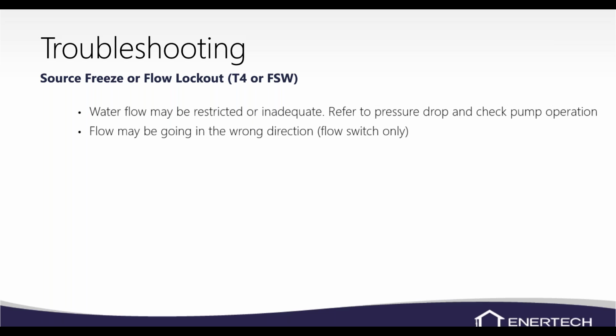Whenever in doubt about the stickers that are placed on the unit, whether they're in the right position or not, refer to the IOM, because it'll tell you. I have seen a few times where the factory put the stickers in the wrong position, and it may not even lock out. It would if you have a flow switch, but it won't if you have a T4 sensor, because the T4 sensor is not actually looking at water temperature, it's looking at refrigerant temperature.